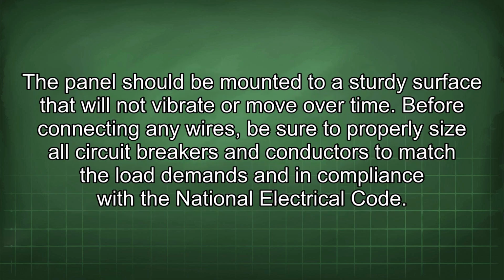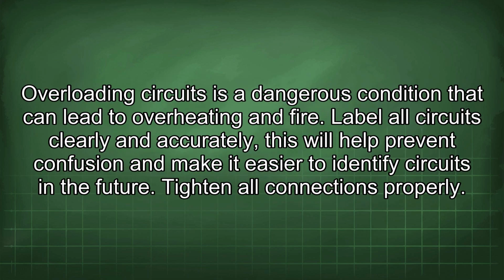The panel should be mounted to a sturdy surface that will not vibrate or move over time. Before connecting any wires, be sure to properly size all circuit breakers and conductors to match the load demands and in compliance with the National Electrical Code. Overloading circuits is a dangerous condition that can lead to overheating and fire. Label all circuits clearly and accurately. This will help prevent confusion and make it easier to identify circuits in the future.